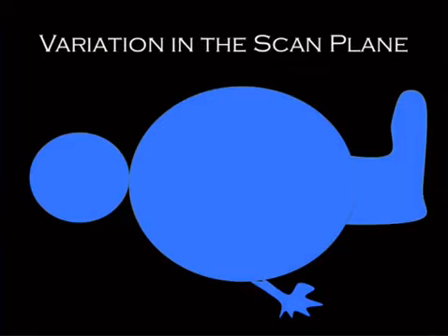So there's a variation with the scan plane. In a regular diagnostic imaging setting, the entrance dose for the skin is much larger than the exit dose, because your low energy X-rays are going to be attenuated early on. In CT, it's different because the scanner spins all the way around and you've got a very highly filtered beam. So the dose is symmetrically distributed, or at least it's supposed to be. Now obviously the center is still going to end up getting less. Body phantoms show that it's about half as much in the middle compared to the edges. So something like this.